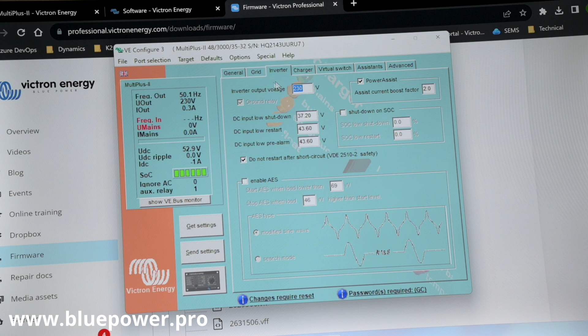Next we've got our inverter tab. So here we can adapt our inverter output voltage. When the inverter is operating disconnected from the grid, it's going to output this voltage. Over here our minimum is 210 and our maximum 240. In some instances I've seen where the grid voltage is maybe 215 most of the time, and then when there's a change or power failure or the power recovery from Eskom, the lights dim or brighten, and that's due to the voltage difference between Eskom and the inverter output. So if Eskom is close to 220, then I would adapt my output voltage to be 220 to match that closer.